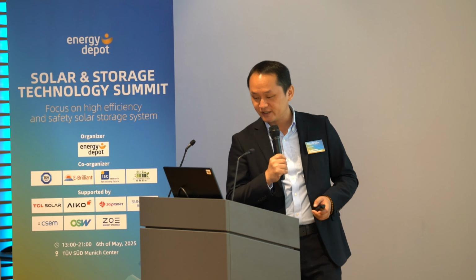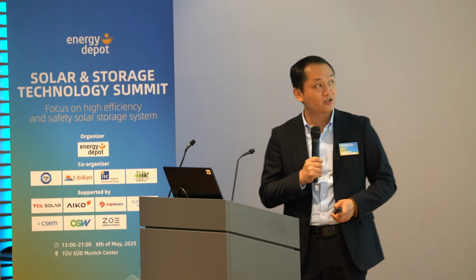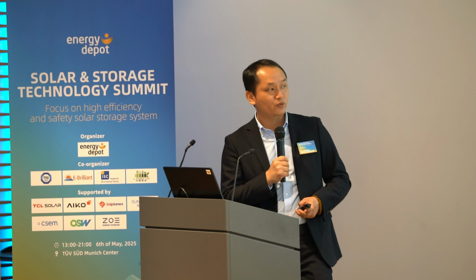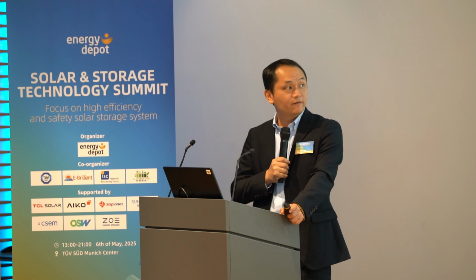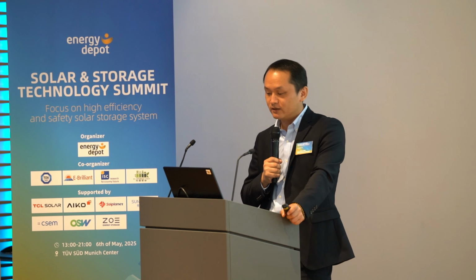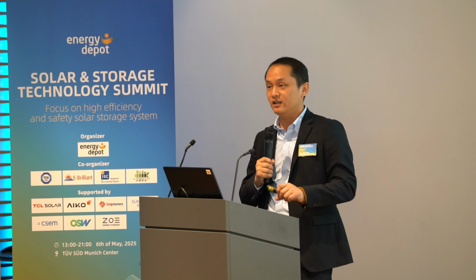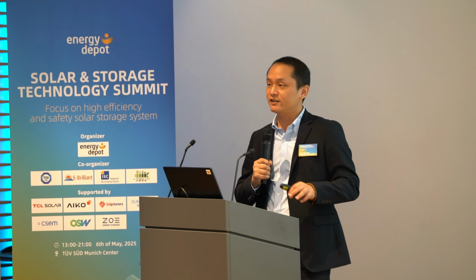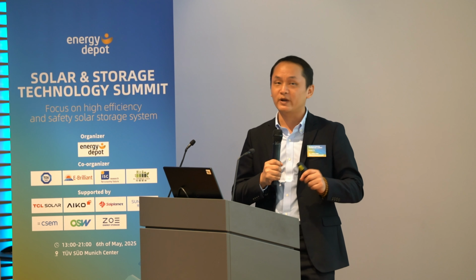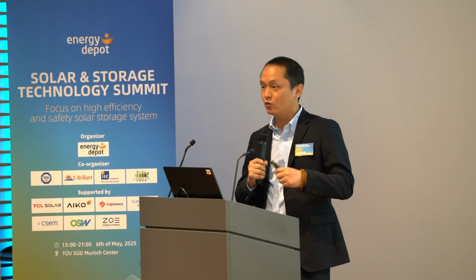The second thing is that when the pack level pressure relief is already working, we will sense flammable gas at the container level, cabinet level sensor, and smoke sensor also. Then the aerosol is released to make sure there is no oxygen for the fire to spread.